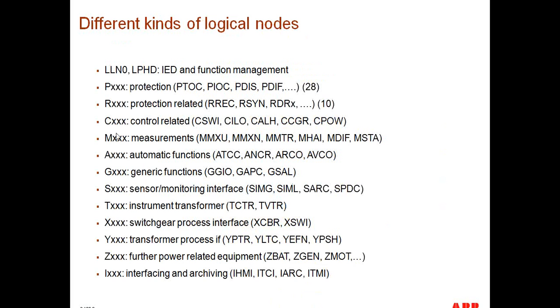These are just some of the different logical nodes that exist, and it's important to see the first letter. It really makes an association with the particular application. So P is protection, R is for related to protection. Some of the things that are related to protection are disturbance recorder, synchronizing functions, auto reclosing. In the case of C, you'll find a whole array of logical nodes related to control, switch controller, breaker controller, interlocking functions. In the case of M, we're looking at measurements. And there's a whole array of measurement functions, current, voltage, phase-to-phase, phase-to-ground functions, and so on.